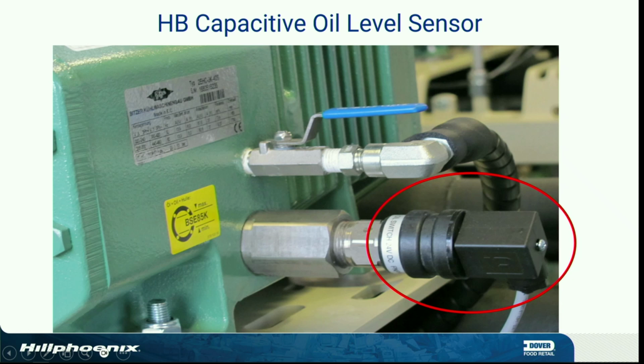Don't put it in. I went to a job site, they were having problems with their oil system. And I walked up and that oil is a honey golden brown. When it's fluorescent yellow, you've added something to it or you've put different oil in it. Fluorescent yellow is not a good color for oil. So you've got a problem, you need to change your oil.